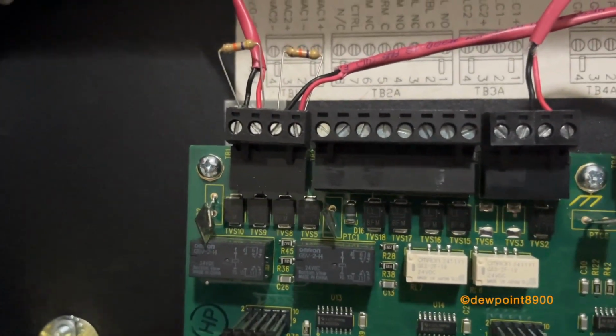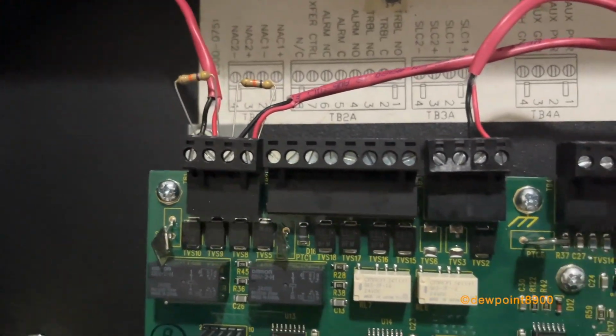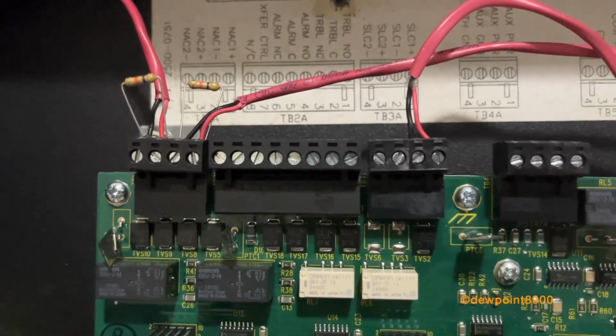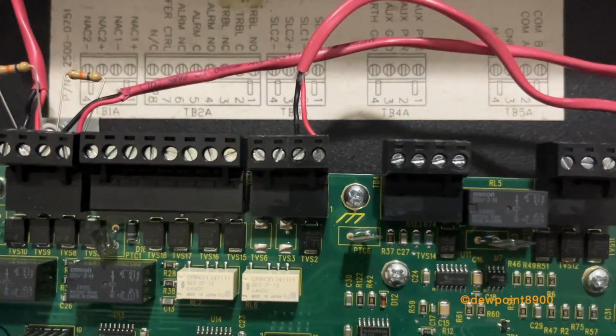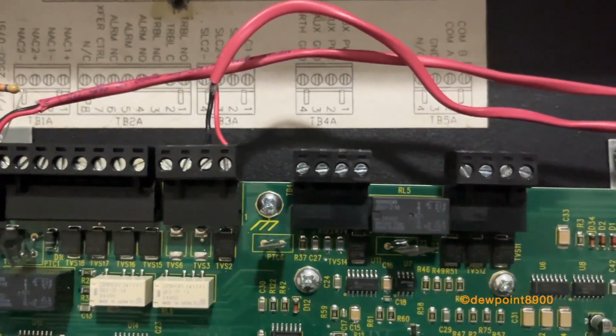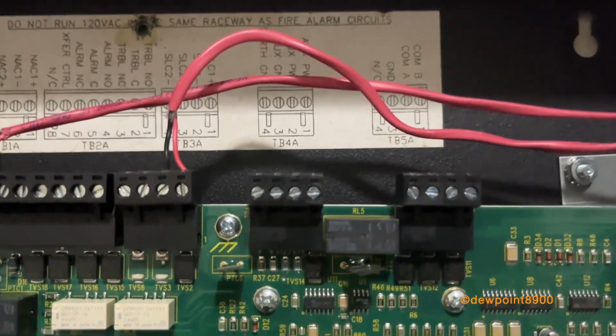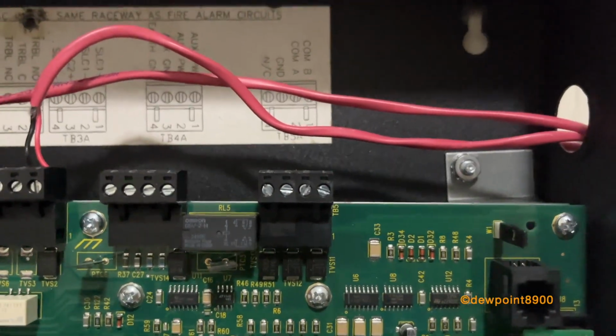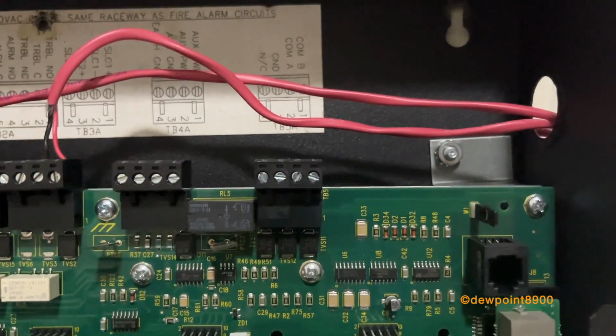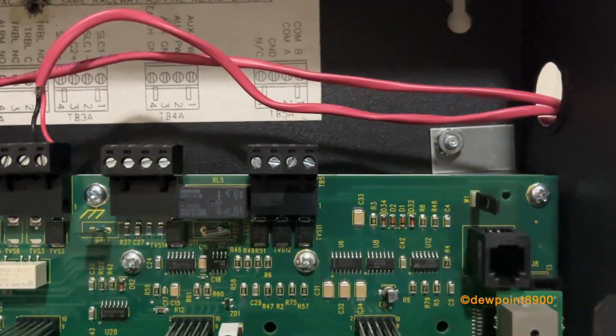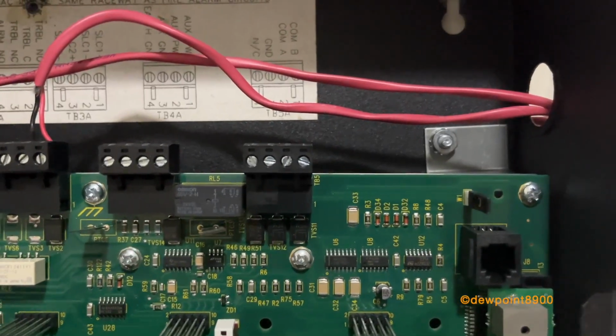So this small terminal block on the top left is the signal circuits, followed by a larger terminal block for relays, a smaller terminal block for the SLC loops, another one for auxiliary power, and another one for communications with annunciators, including the LCD7100 or the RAN7100.